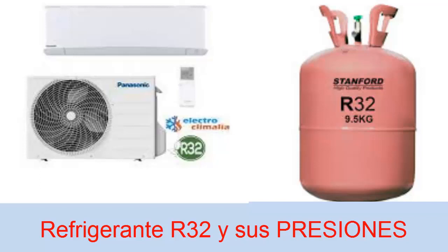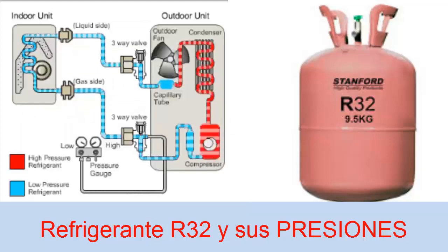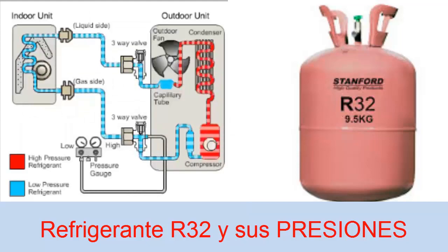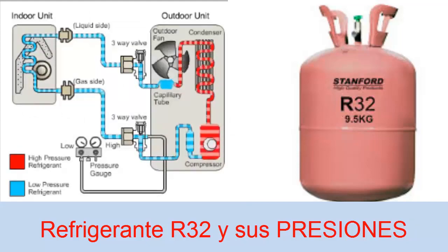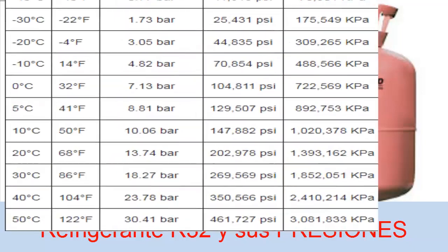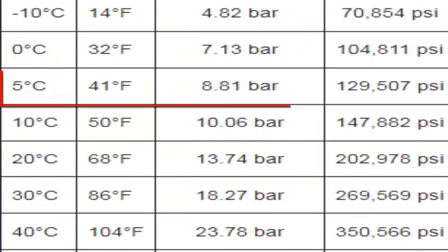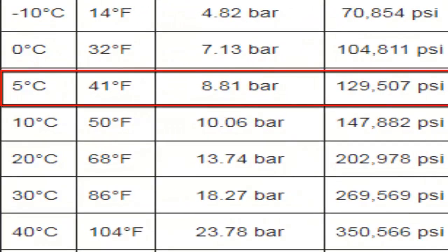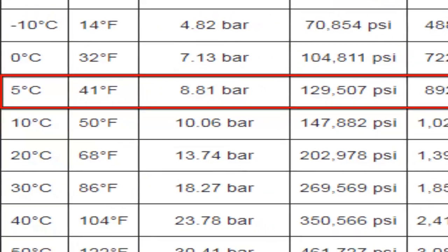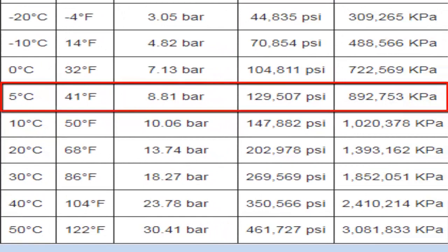For this application, generally the temperature in the evaporator is very close to 5 degrees Celsius. For this temperature of 5 degrees Celsius, we are going to have a pressure close to 129 PSI A — higher than that of the refrigerant R410A.